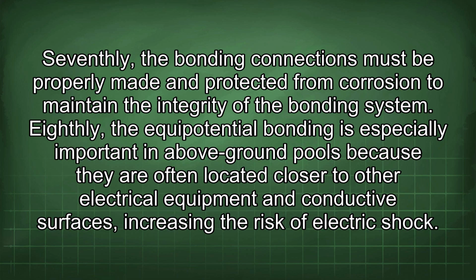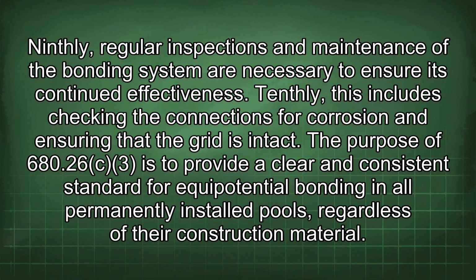Eighthly, the equipotential bonding is especially important in above-ground pools because they are often located closer to other electrical equipment and conductive surfaces, increasing the risk of electric shock. Ninthly, regular inspections and maintenance of the bonding system are necessary to ensure its continued effectiveness. Tenthly, this includes checking the connections for corrosion and ensuring that the grid is intact.